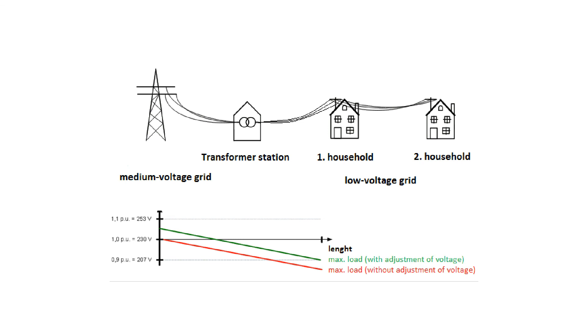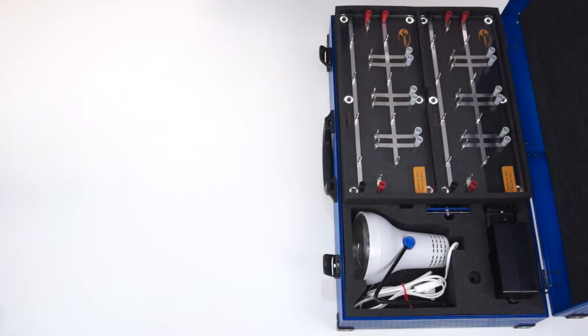In Germany, the nominal value of the voltage of 230 volts has been defined and may vary for a secure supply to a maximum of only 10% of this value. With the installation of private photovoltaic systems, it may cause over-voltage. We want to simulate this issue in a trial with the smart grid components.